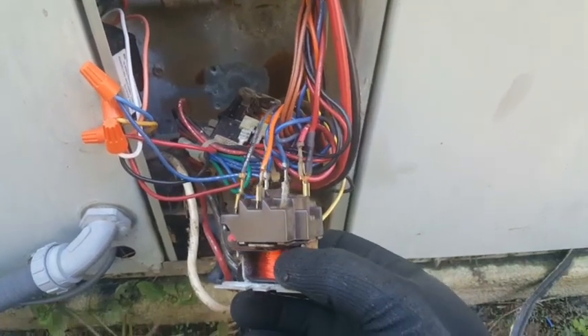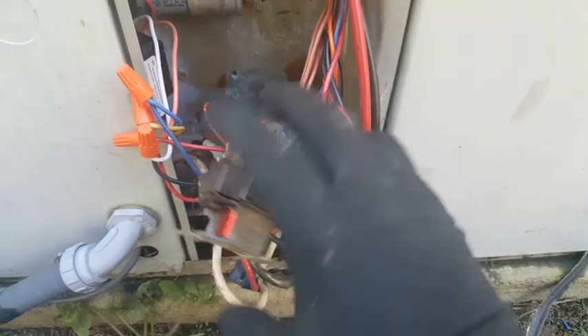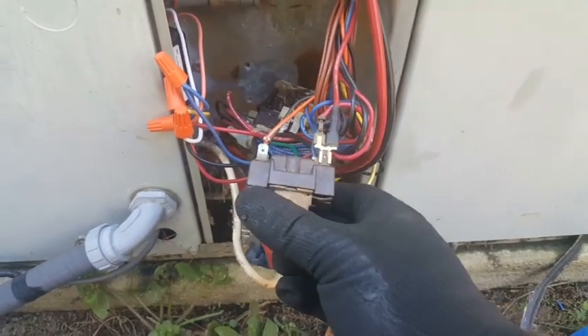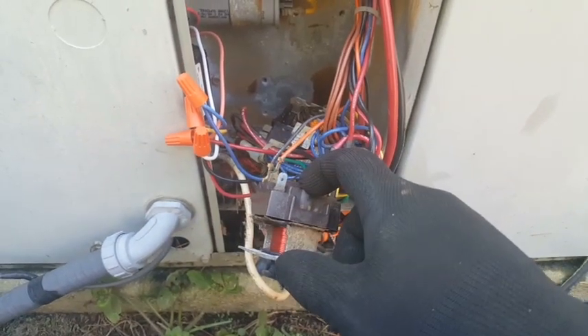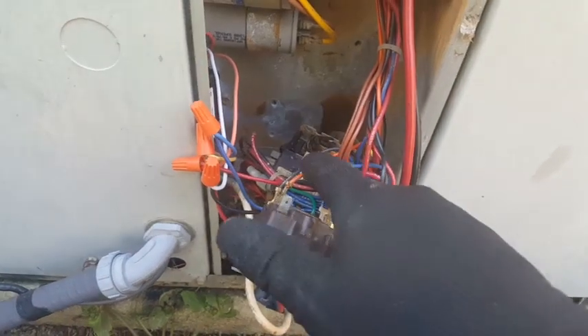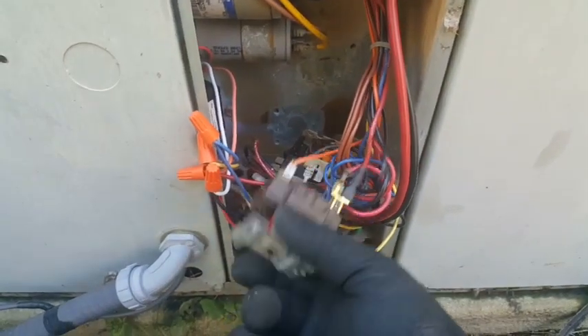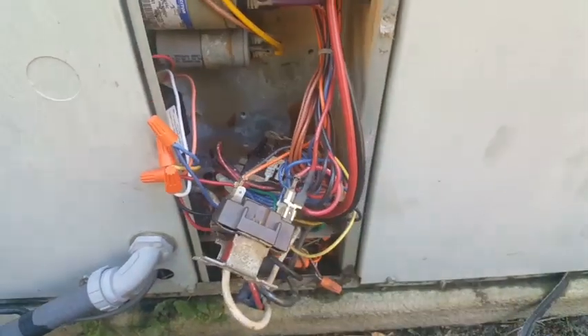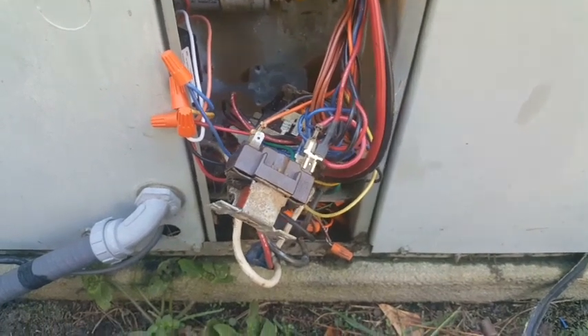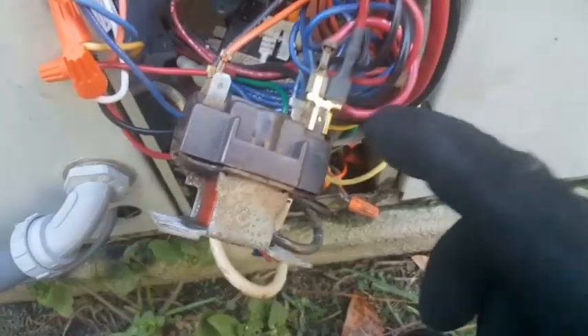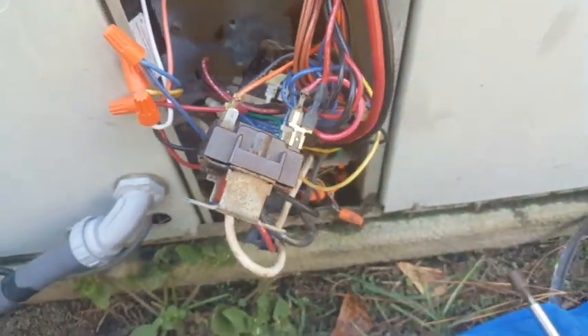Now this one had no evidence of failure, but I wanted to go ahead and replace all the electronics that were underwater just for safety purposes. And since it's not that much of an expense just to go ahead and switch this one out, because the transformer was blown and the contactor was shot, those were for sure. So I figured, you know what, go ahead and throw a double pole, double throw on there just for safety purposes. So we're going to go ahead and put that in and have it jumped off here so the blower would run, but I'm going to redo that.